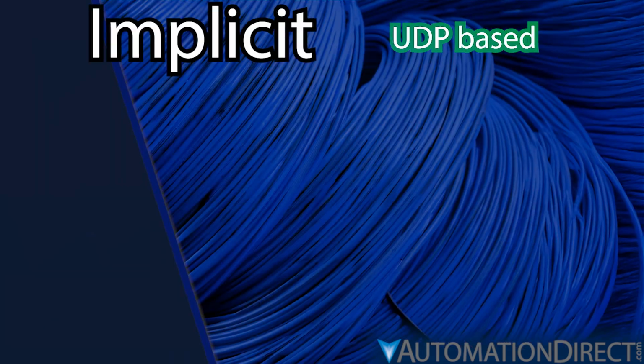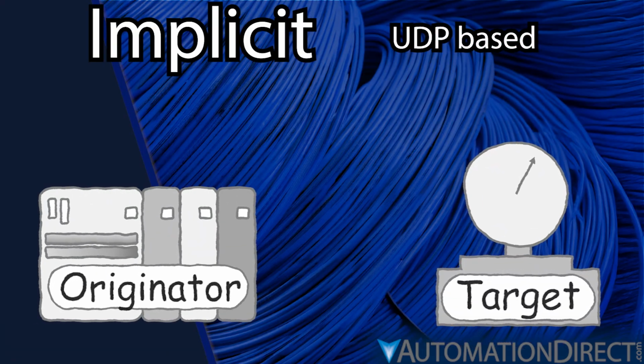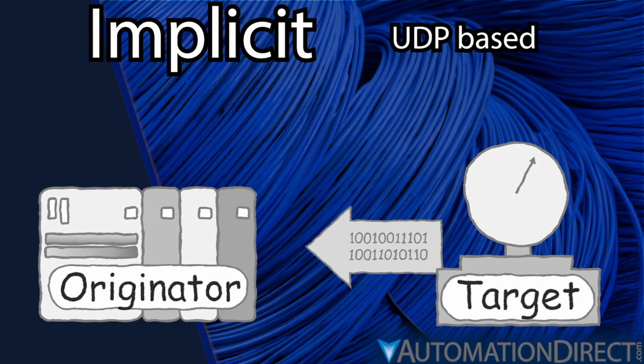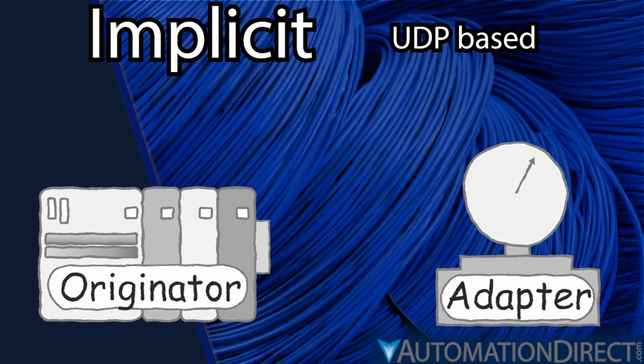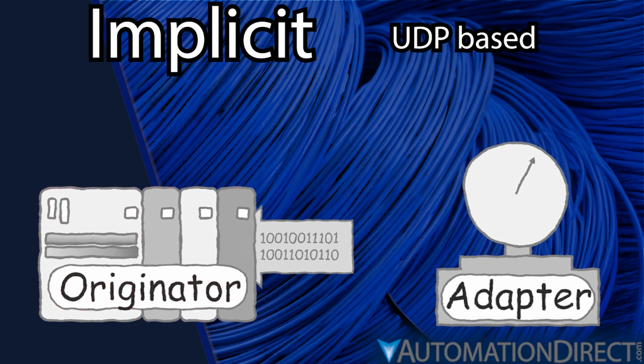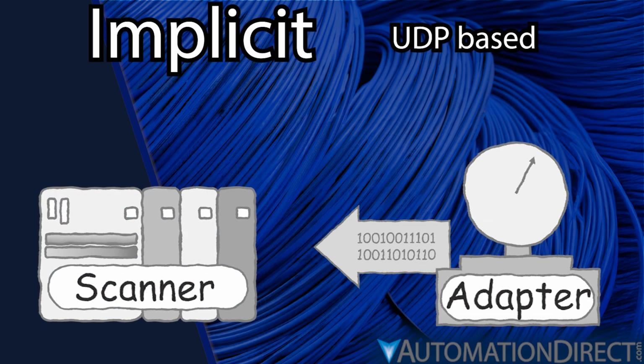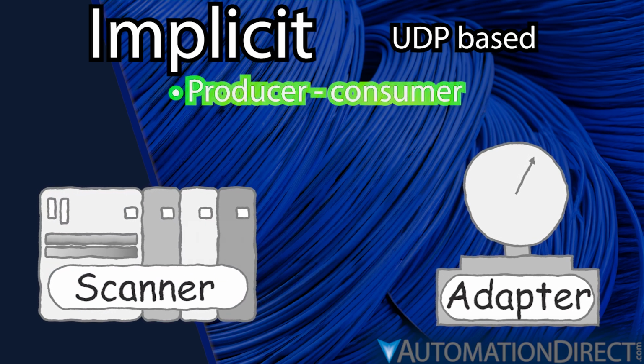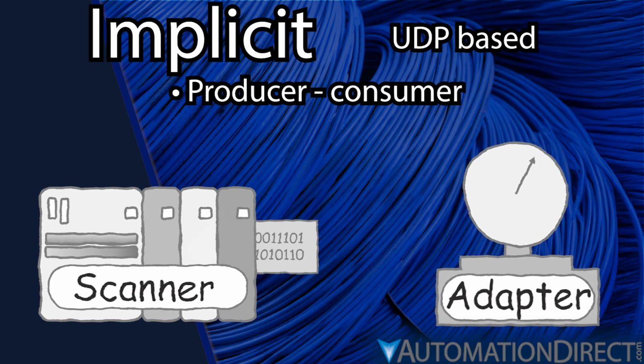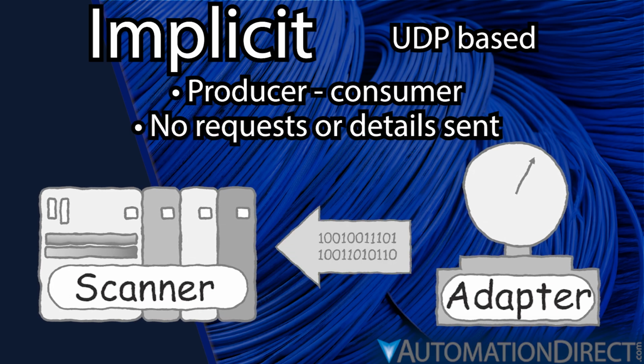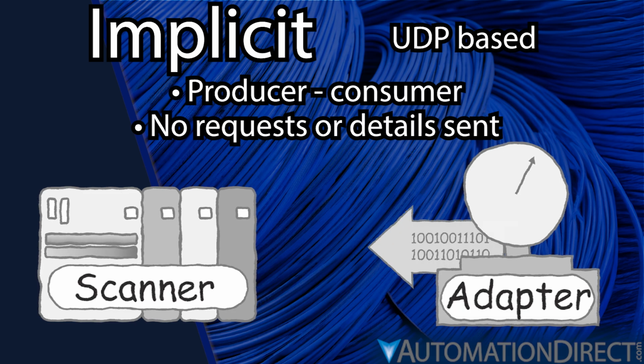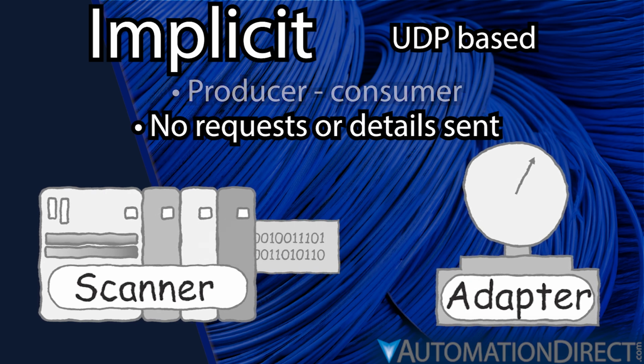Implicit messaging, sometimes called I/O messaging, on the other hand, employs a constant stream of data from the target device, called an adapter, to the originator, called a scanner, transmitted via UDP. Implicit messaging fits a producer-consumer communication model. There are no requests and no information about what the scanner needs, no handshake checks, and no receipt acknowledgments.